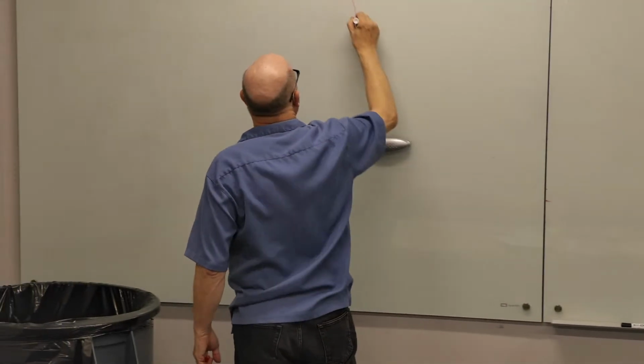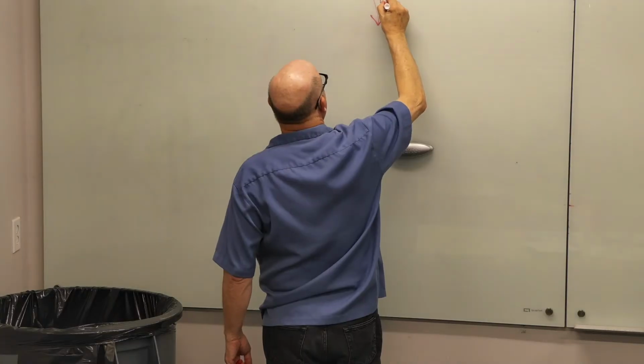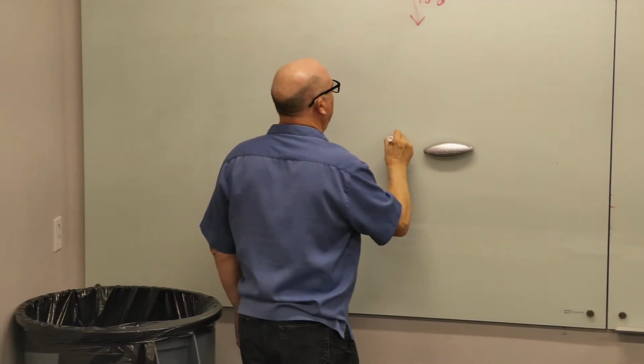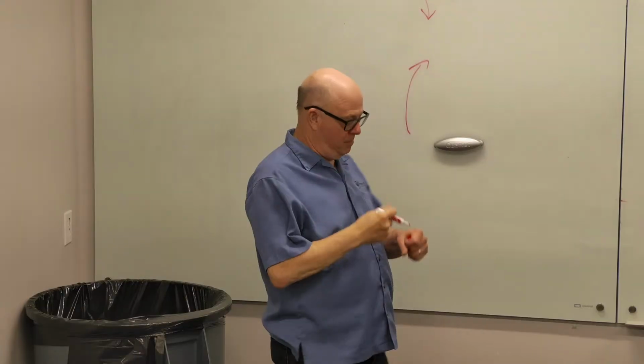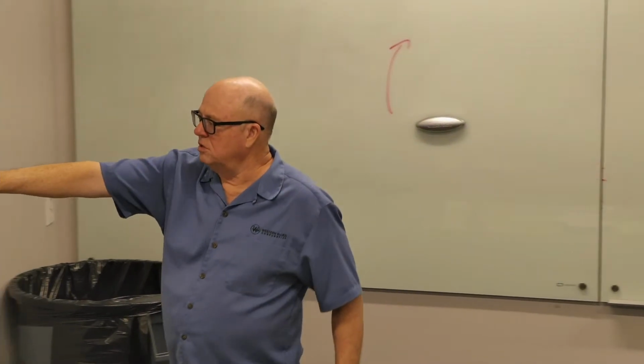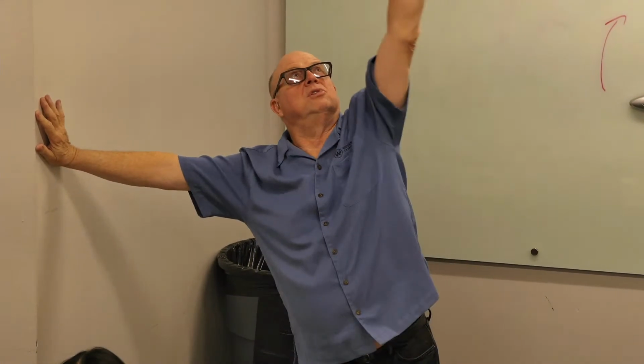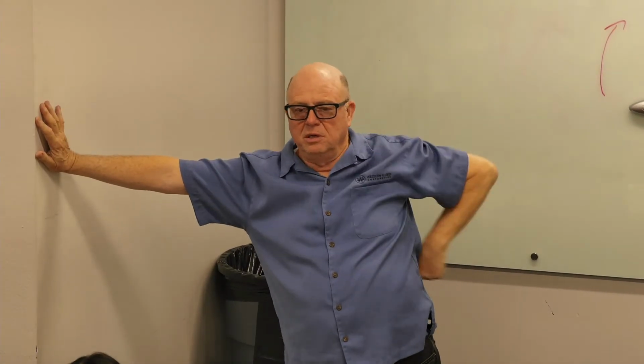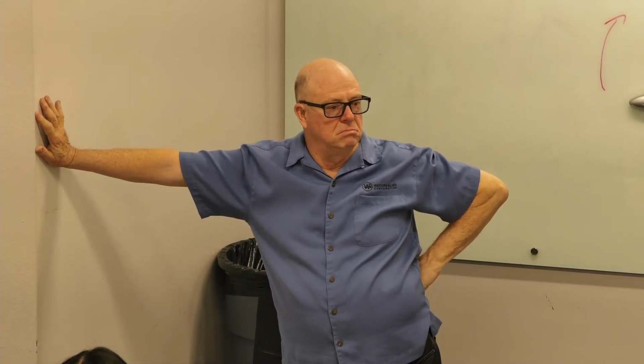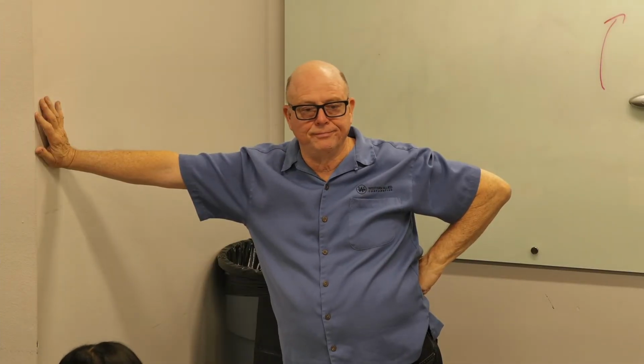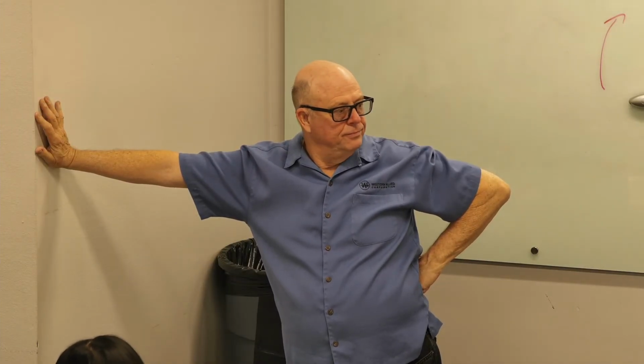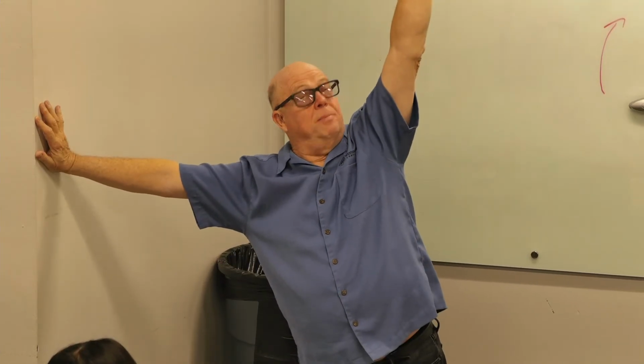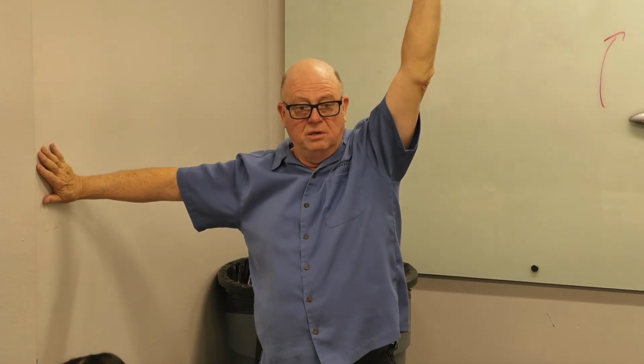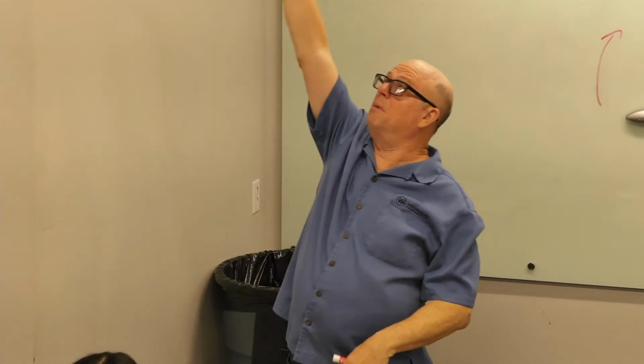So let's say we were bringing in 15% outside air. And the return air from the building, if it's 72 on the wall, what's the temperature up in the return air plenum of the ceiling? Más o menos. Well, first of all, is the temperature just right below the ceiling going to be the same as it is here on the wall? Heat rises, doesn't it? So if it's 72 here, it's probably, I don't know, 74 up there at ceiling level.